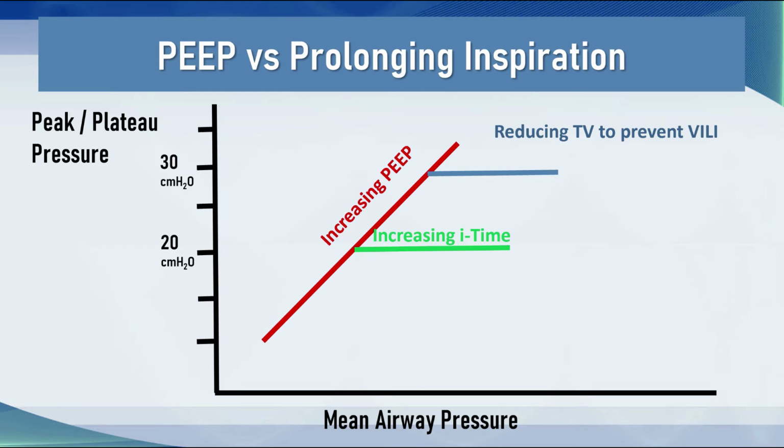And you can see here, as I've shown you in previous pictures, that the plateau pressure will stay stable as the increased inspiratory time goes on, but there comes a point where you run into trouble, and the trouble you run into is Auto-PEEP if the tidal volumes or the driving pressures are maintained.